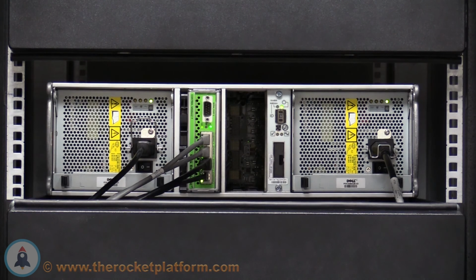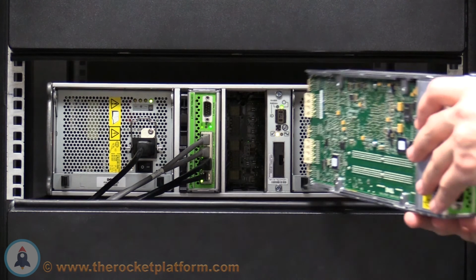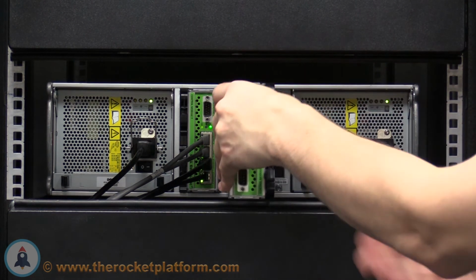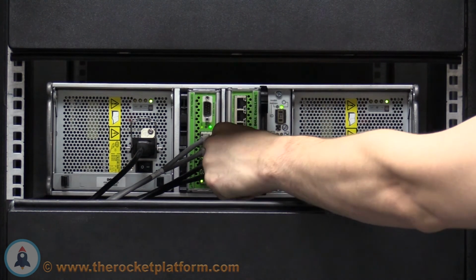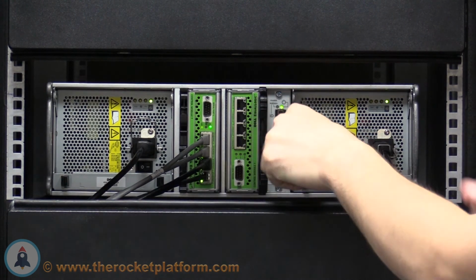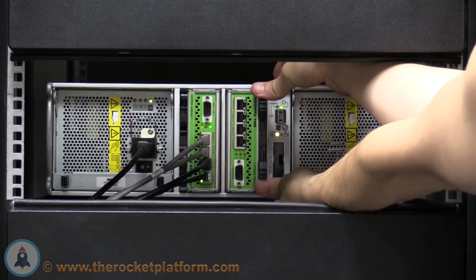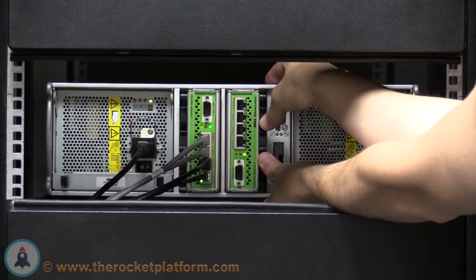Open the levers on the replacement controller all the way. Then insert the controller into the now open slot. Make sure the controller is oriented in the same direction as the controller that was just removed from the slot. Once seated around 90% of the way, the black levers should catch in the slots they lock into. Once the levers begin to catch, push the levers shut inwards, which should cause the controller to seat the rest of the way.